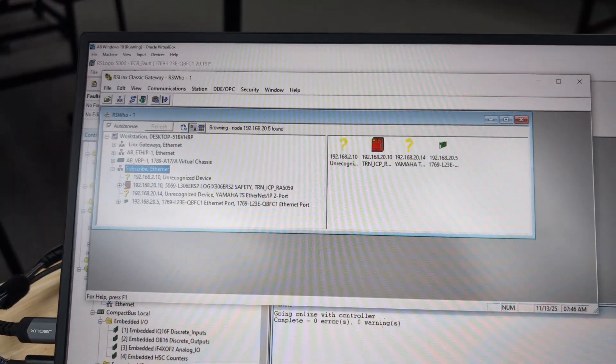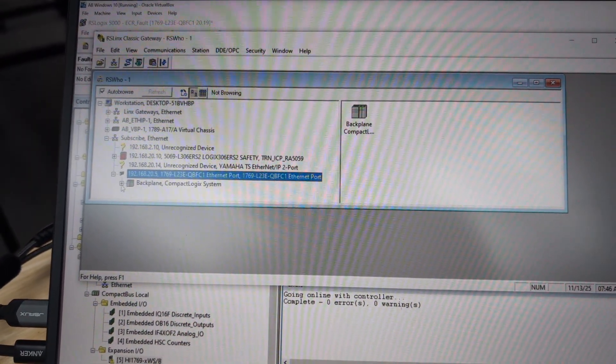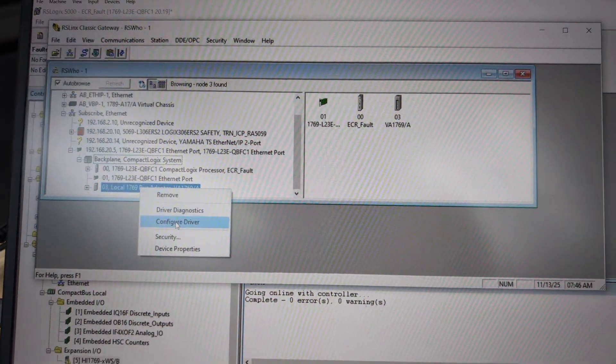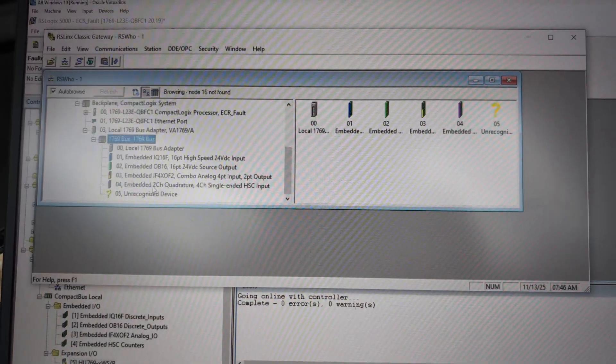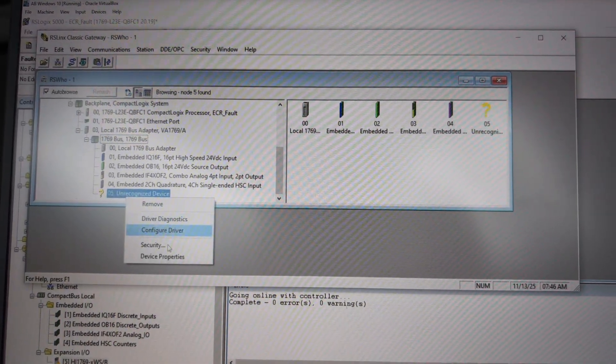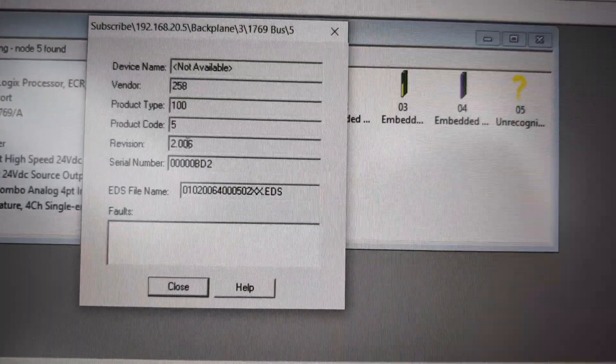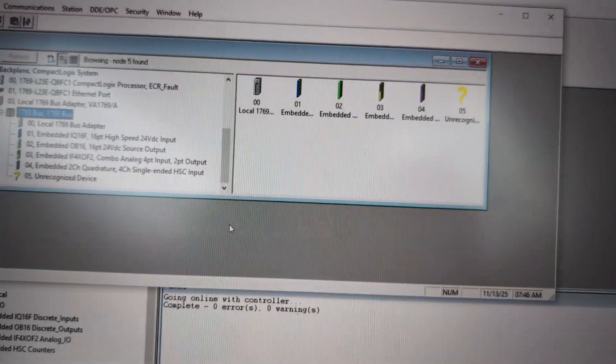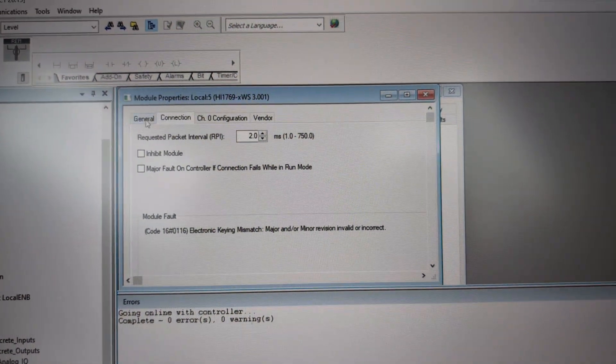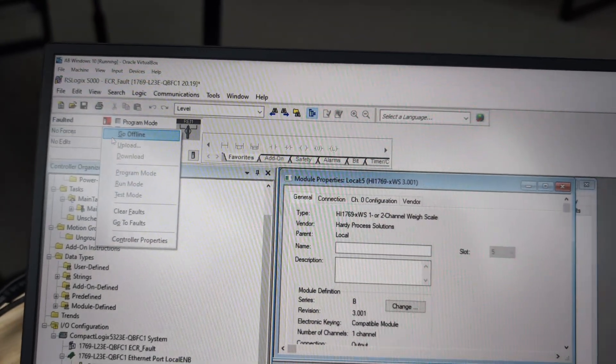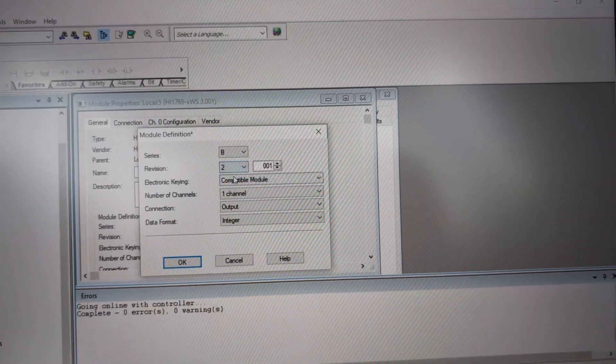We're going to jump over here to RSLinx and have a look at it over here. That's not what we're looking for. We're looking for this unrecognized device properties. Says it's revision 2.06 and over here what did I put in? Revision 3. Okay, well let's go offline and we'll change that over to revision 2.